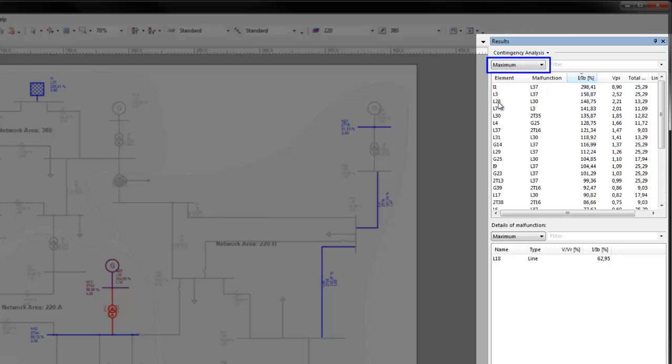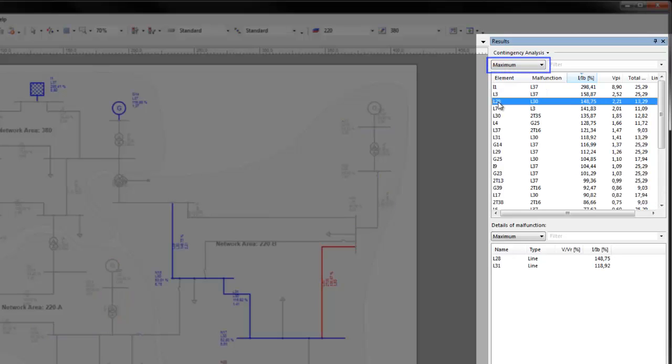In maximum, all network elements are listed with their respective most critical malfunction. In this example, the element L28 will reach its highest utilization, 148%, by the malfunction of element L30.